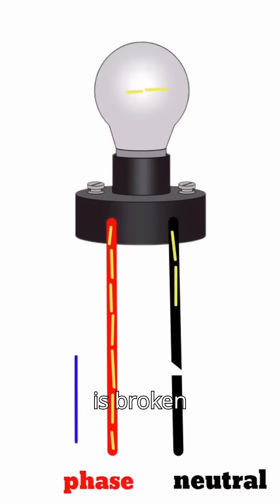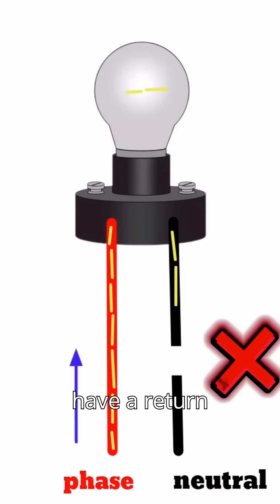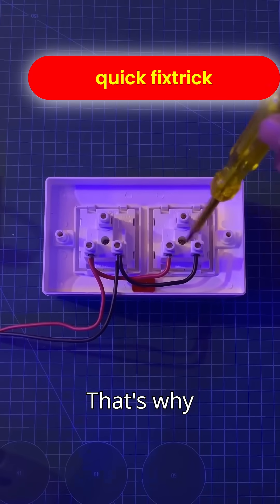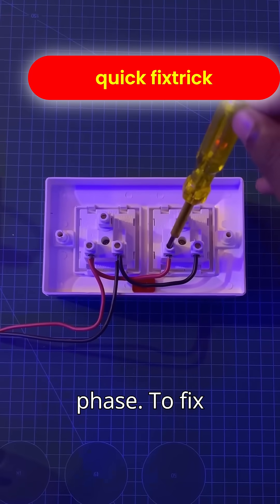If the neutral wire is broken anywhere in between, the current won't have a return path, so it can't return and voltage starts to appear in our neutral wire. That's why both sides of the socket start showing phase.